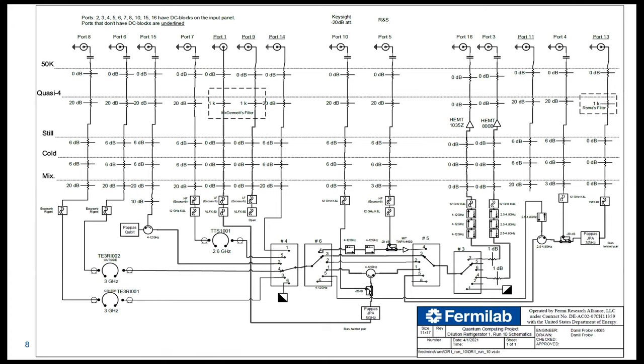And ultimately, on average, depending on how hard you drive your cavities and how much RF power you send there, the temperature is around 19 or 20 millikelvin. But if you turn off everything and let it cool, I think it will cool down maybe to 12 millikelvin. And if you remove some devices and reduce the heat load, it can cool down to 8 millikelvin. So in our case, we normally operate, as you said, from 15, maybe 14, up to 20, 25 millikelvin.